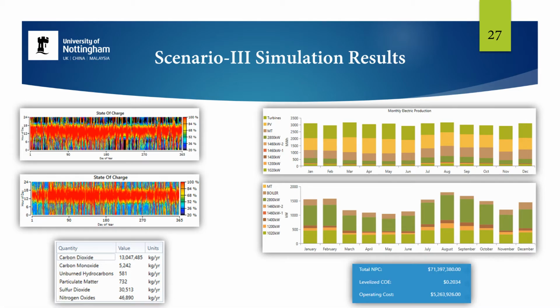the rapid discharging and charging of batteries were eliminated in order to increase the life expectancy of battery units. So as you can see, in most cases, the dispatch strategy actually waits until the battery reaches 20% of energy content and then attempts to charge the batteries.